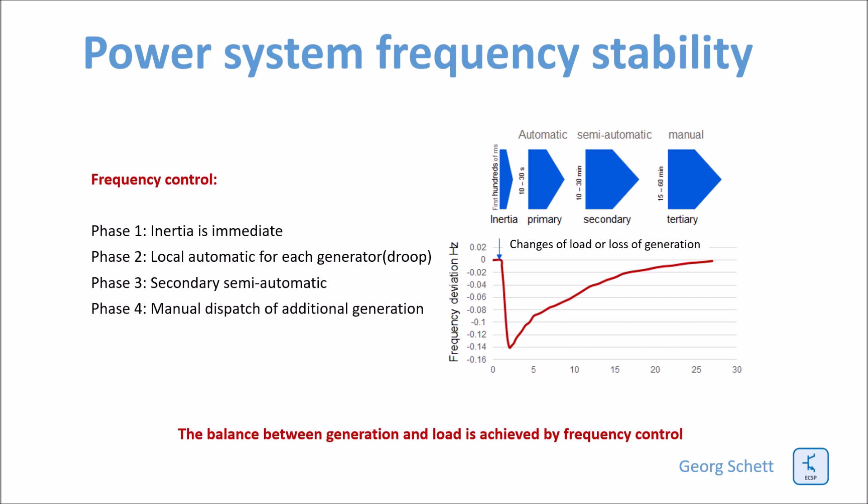In a second phase, there is a very local generation control. It's the so-called droop, which is opening or closing the valves, for example, of steam engines or of hydropower plants.